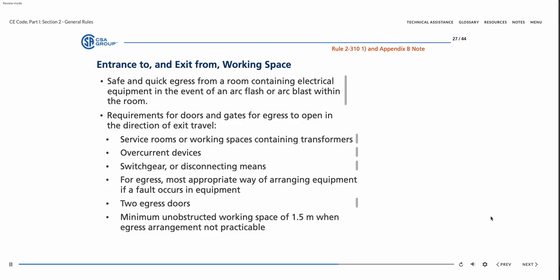When such egress arrangement is not practicable, the equipment must have a minimum unobstructed working space of 1.5 meters. When a room is large relative to the required working space, the National Building Code of Canada may allow doors or gates located more than 7.6 meters away from the working space to open in either direction.